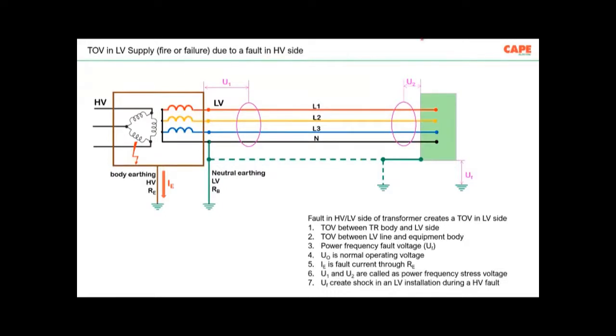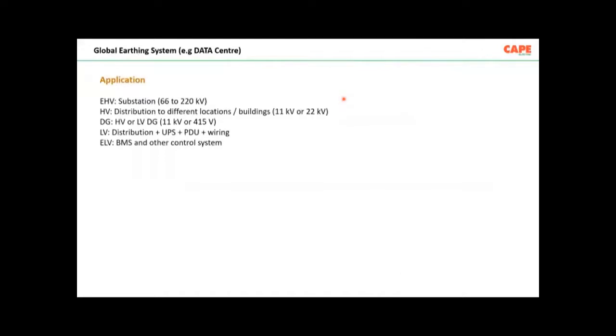Three problems, as I said. One is your transformer may fail. Anyway, it's outside, you don't need to bother. The second is most of the time your equipment may fail. The third problem is you may get a shock. A person who is touching some part, let us say somebody touching the refrigerator, will get a shock. RCDs are not practically possible. RCDs will not work under this particular condition. So earthing has actually very, very important roles to limit the temporary over voltages and shock voltages inside your equipment.